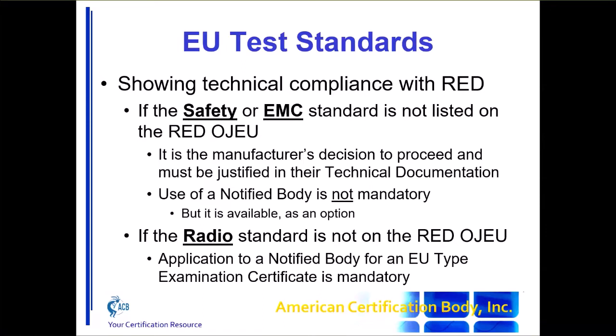A notified body certificate is not mandatory just because the safety or EMC standards are not listed on the OJ. You can get a notified body certificate and it could be useful, but it's not mandatory. It's only if the radio performance standard is not listed on the Official Journal that the notified body certificate becomes mandatory.